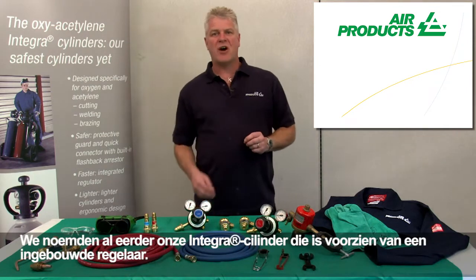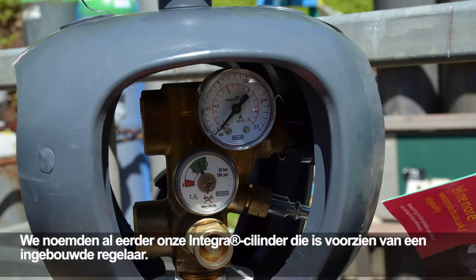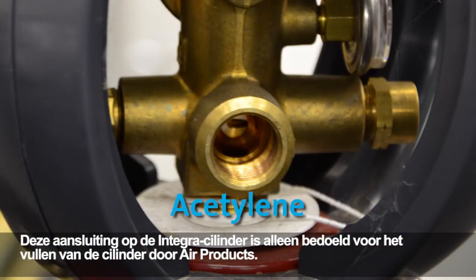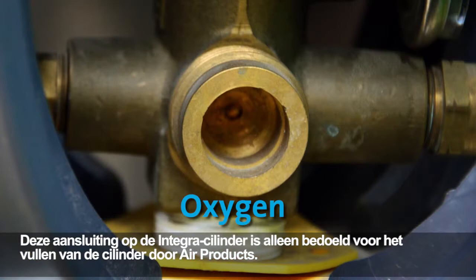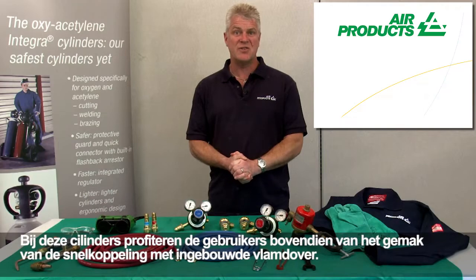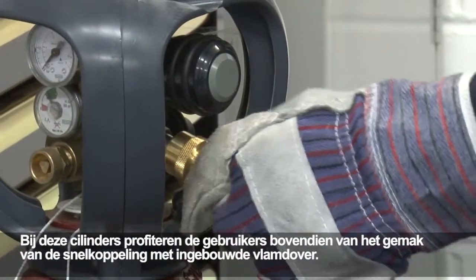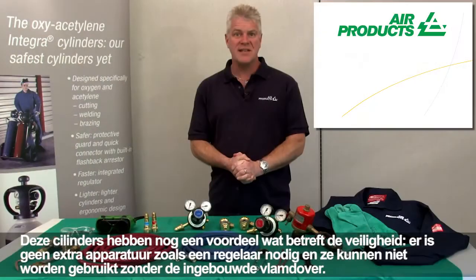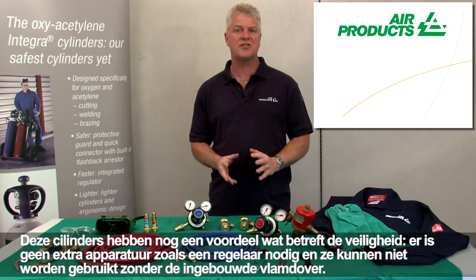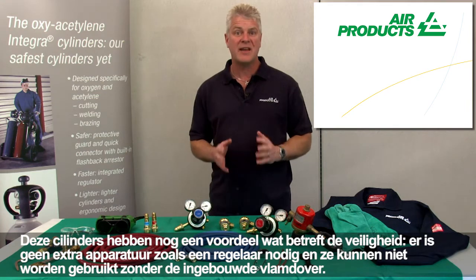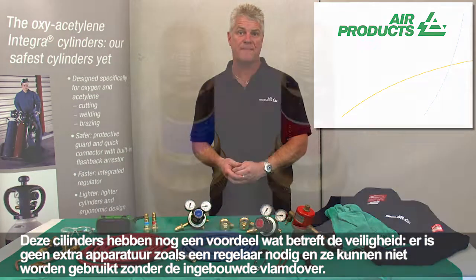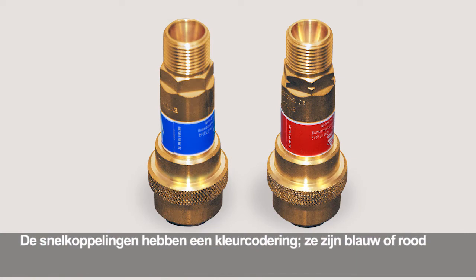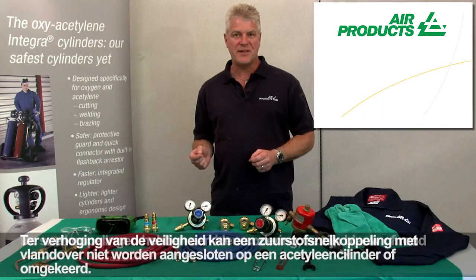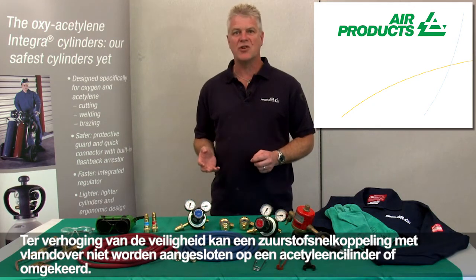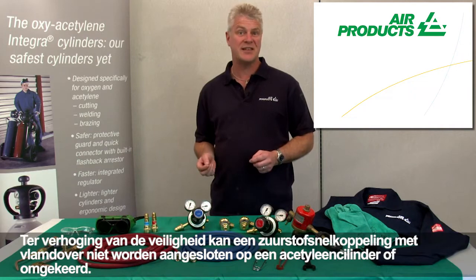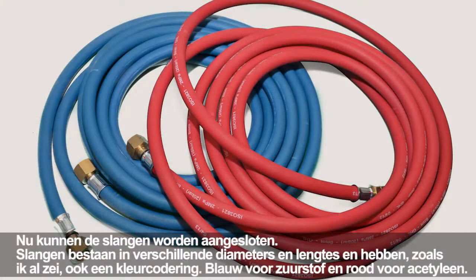We spoke earlier about our Integra cylinder, which includes a built-in regulator. This port on the Integra cylinder is only for air products to fill the cylinder. With these cylinders, users have the added convenience of a quick fit connector which incorporates a flashback arrestor. These cylinders have the added safety benefit that no additional equipment such as regulators is required, and they can't be used without the built-in flashback arrestor. The quick fit connectors are colour-coded, blue and red respectively. For increased safety, it's not possible to connect an oxygen quick fit flashback arrestor to an acetylene cylinder or vice versa. Next, fit the hoses.